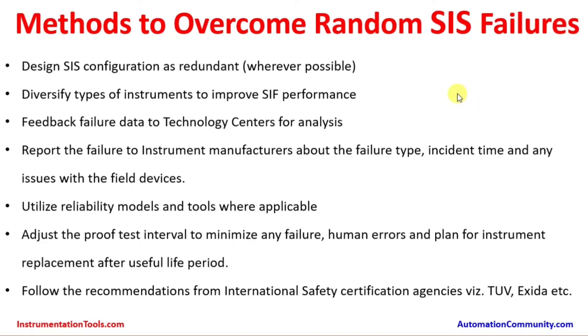Methods to overcome random SIS failures include: designing SIS configurations as redundant wherever possible; diversifying the type of instruments to improve safety instrumented function (SIF) performance; feeding failure data back to technology centers for analysis when there are multiple and repeated failures; and reporting failures to instrument manufacturers about the failure type, incident time, and any issues with field devices, so that design improvements can be made.